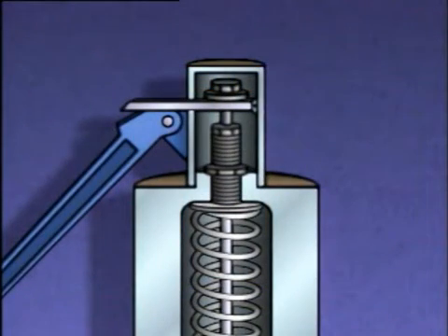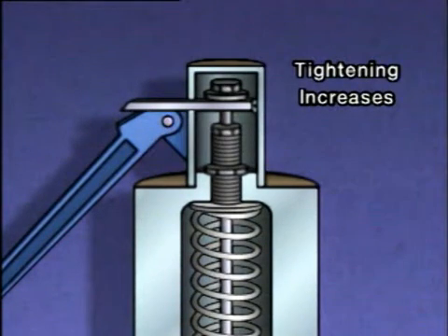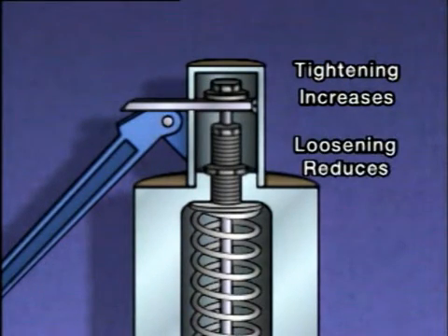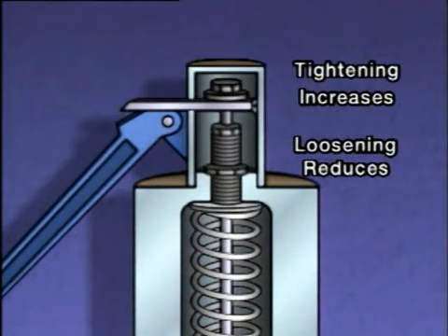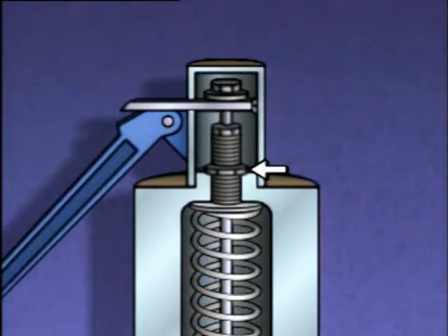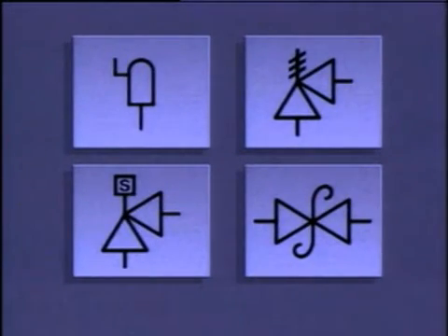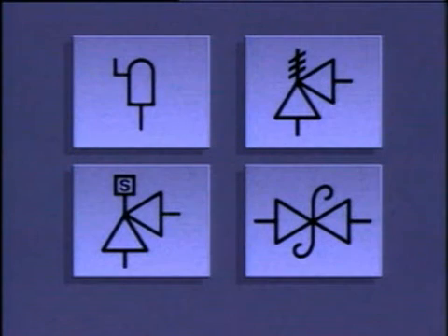The opening pressure setting can be changed using the adjusting screw. Tightening the adjusting screw increases the force exerted on the disc, thereby raising the pressure setting at which the valve opens. Loosening the adjusting screw reduces the amount of force on the disc and allows the valve to open at a lower pressure. The lock nut holds the adjusting screw in position after the force exerted by the spring has been set. On a piping system diagram, a safety valve could be represented by any of these symbols. These symbols are similar to the ones used to represent relief valves.